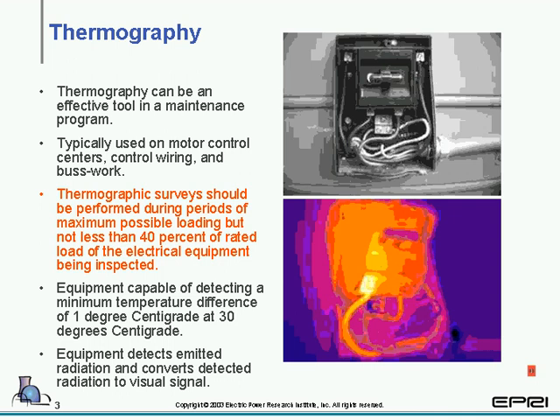Now, when you get to the larger type breakers, such as your metal-clad low and medium voltage, you can use thermography except for the fact that with the arc chutes, phase barriers, and protective coverings, you may not actually see the hot spot as shown in this picture here. You may see heat or a warmer spot somewhere, but nowhere near as good as in this picture.